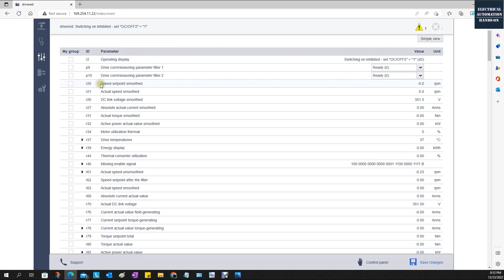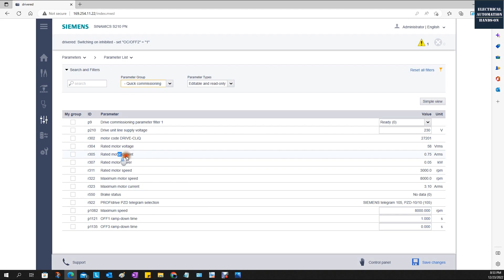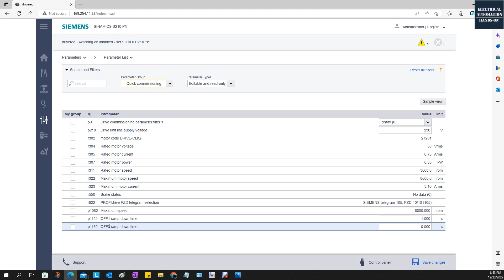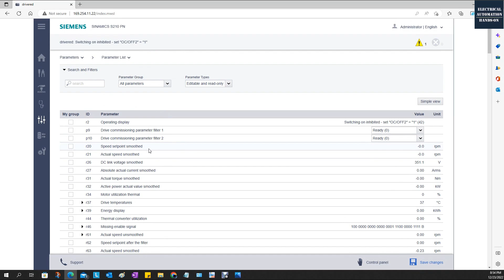So from this parameter list, you can group them and set some important parameters. For example, for the communication, you can especially focus on the communication parameters. Or for the quick commissioning parameters, you can fill in all those values from the motor: rated current, rated power, rated speed, and the maximum speed, ramp down, and those time settings, all those ramp down times for the OFF1 or OFF3. So once we shut down the power, how fast the motor will stop, those parameters are used for this. So the parameter list is very useful.